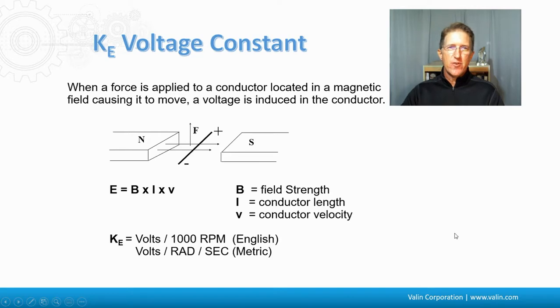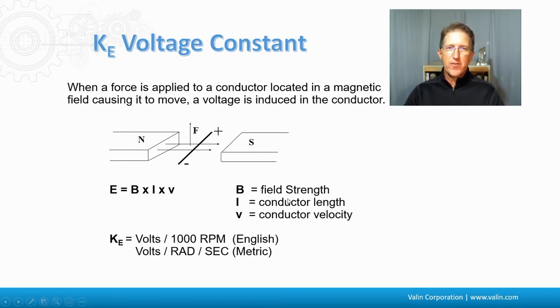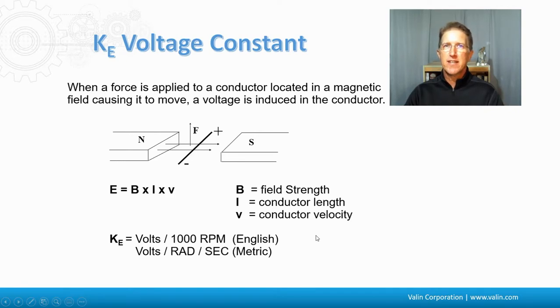There's also a KE voltage constant, defined by when a force is applied to that conductor located in the magnetic field, causing it to move — a voltage is induced in that conductor. This is the product of the field strength, the conductor length, and this time the conductor velocity. It ends up with units of volts per thousand RPM or volts per radian per second, again depending on English or metric.